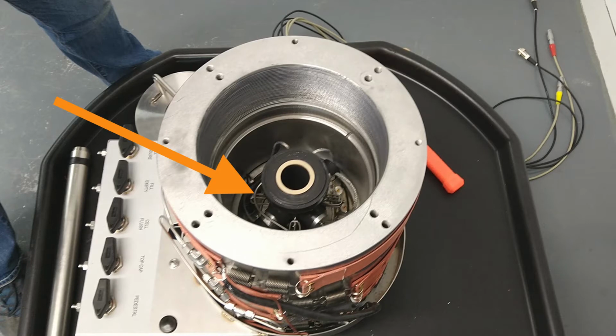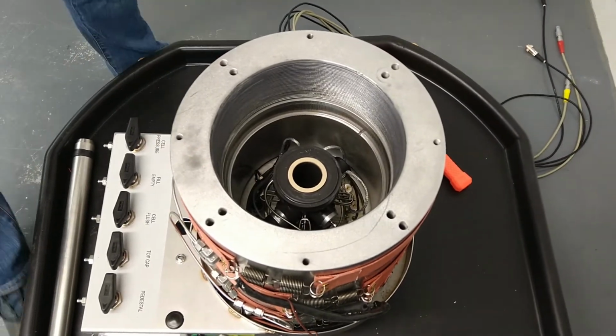Locate the bleed pipe inside the upper lip of the membrane. This will be used later when filling the cell with oil, to remove the pocket of air that will form within this space. If not already done, apply silicone grease to all sealing surfaces of the sample membrane. Place a small fixed ring into the membrane with the chamfer facing downwards.